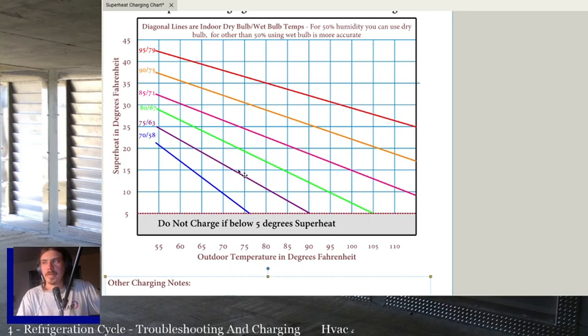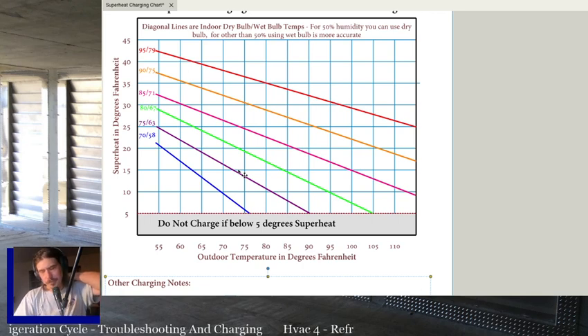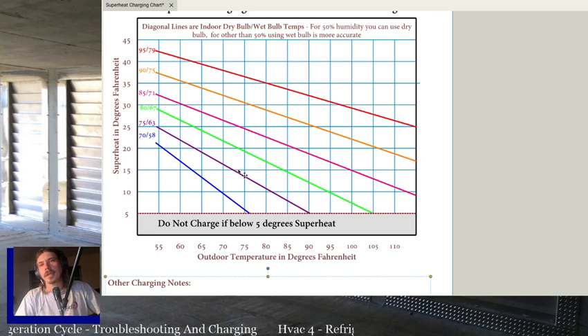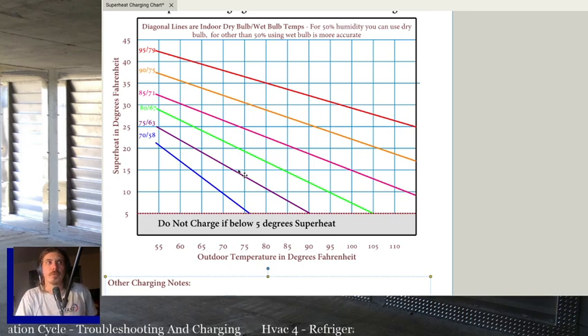The outlet of the evaporator, ideally, but usually we measure it at the outdoor unit. On the suction line, preferably at the outlet of the evaporator, but as long as you're on the line, you shouldn't have a pressure drop across the line set. So as long as you're measuring somewhere in the line set, it should be accurate enough if everything else is okay. But if you suspect an undersized suction line or a restriction, you're going to have other issues messing things up too. If you suspect a slightly undersized suction line, or the suction line's uninsulated and running through a hot attic for whatever reason, and you're not going to fix that right now, measuring at the evaporator outlet is important. If you're doing retail reach-in coolers and stuff like that, you need to be at the outlet of the evaporator, because everything changes when all those things manifold together. But otherwise, as long as you're measuring superheat somewhere in that line set, you should be fine.